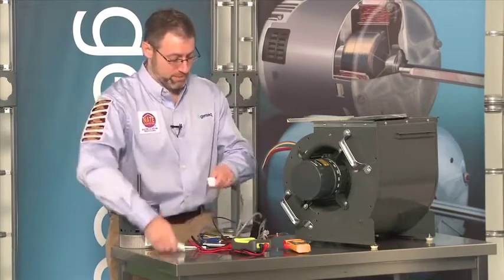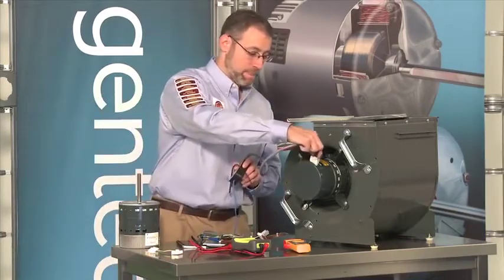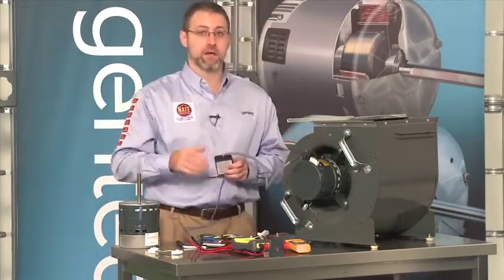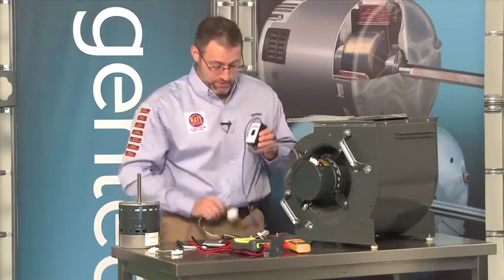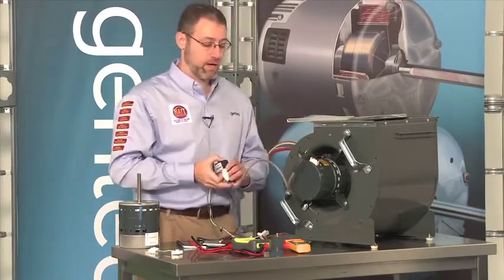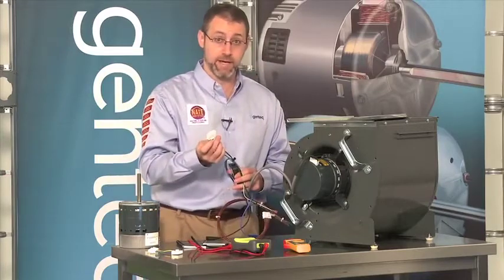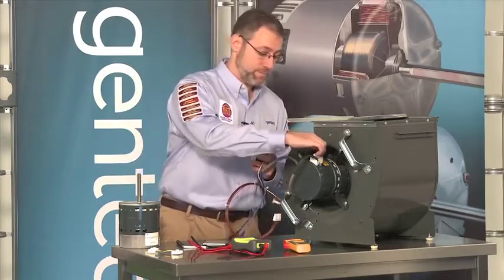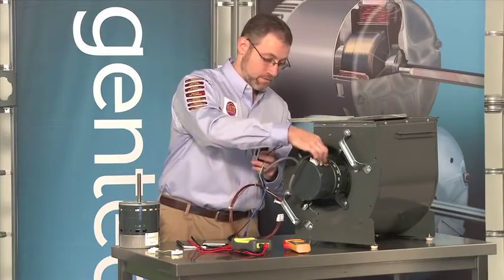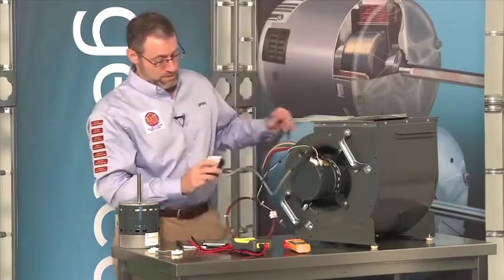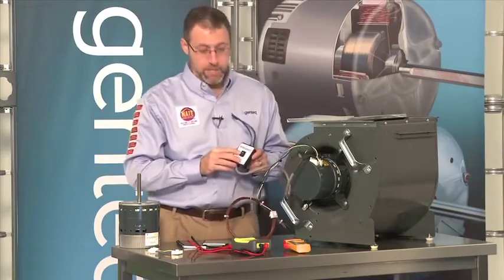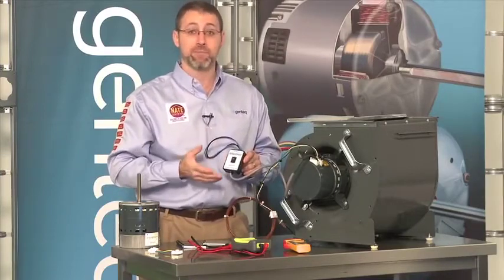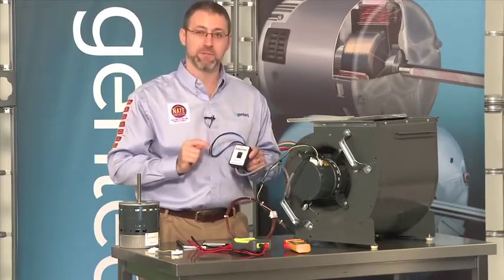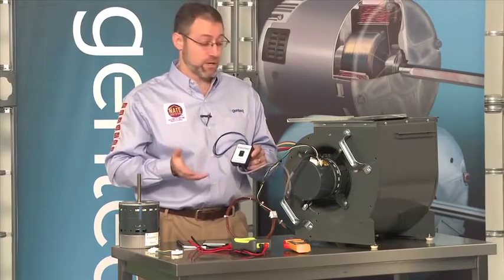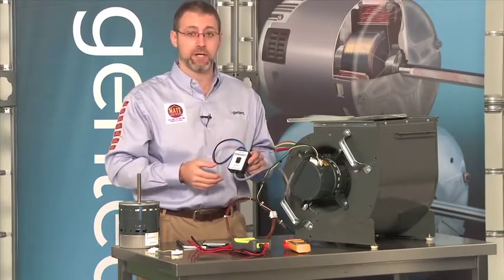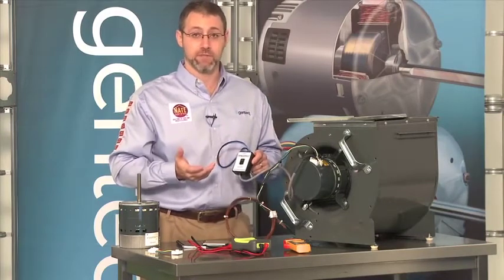All right, so let's put the TechMate back into the motor. Now this is a running test, so we do have to have power on the motor. So of course we've got the power off. We're going to plug our 5-pin connector back in, which we've already confirmed we have power on. We double check to make sure we're plugged in on our TechMate and we have a green light. And the next step is really difficult. We flip the switch. And that's really all there is to it. We should get a go, no-go operation out of the motor from this very simple test.